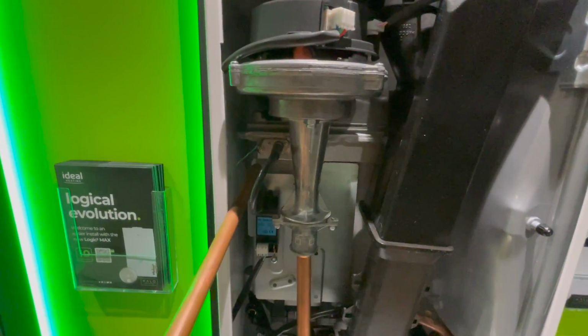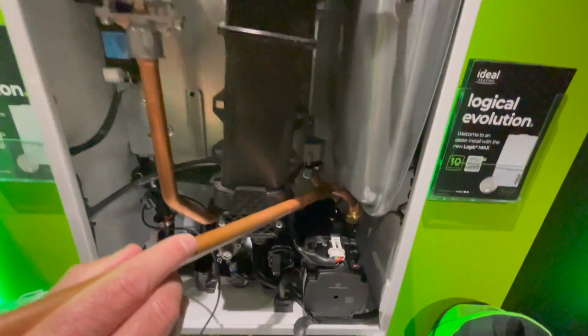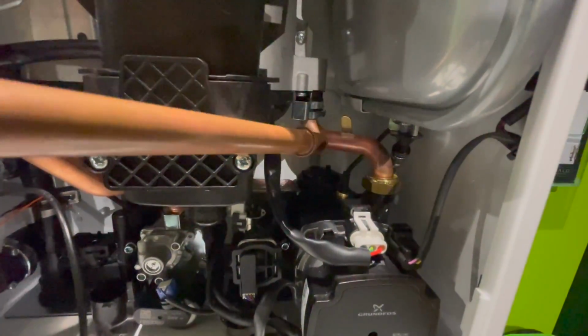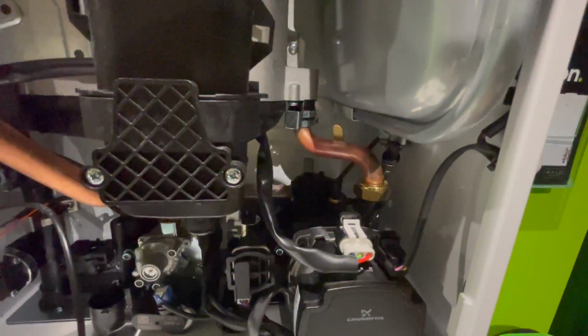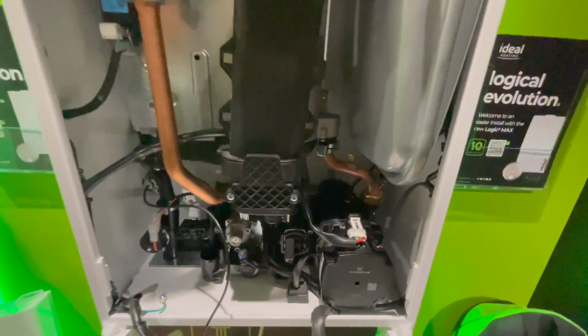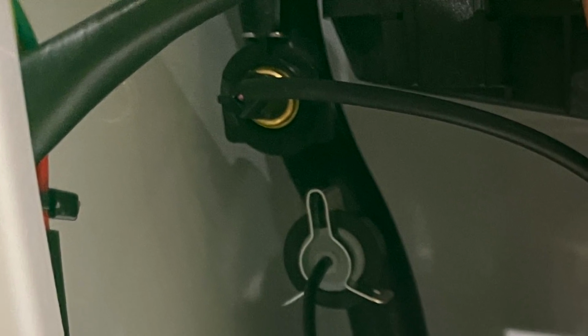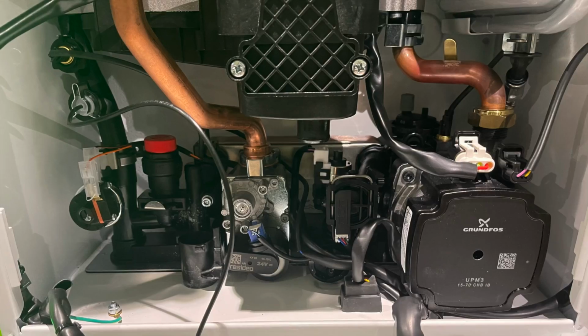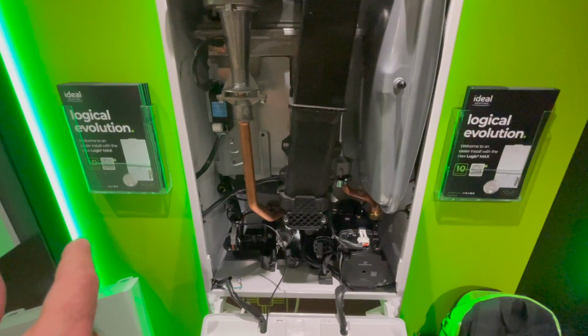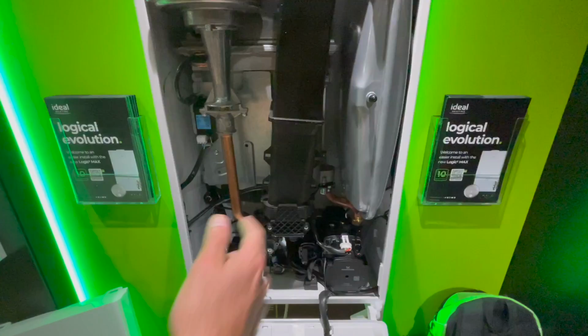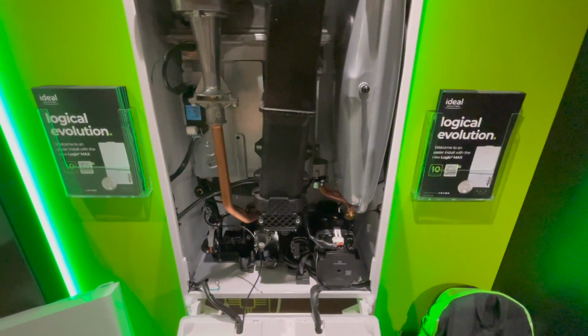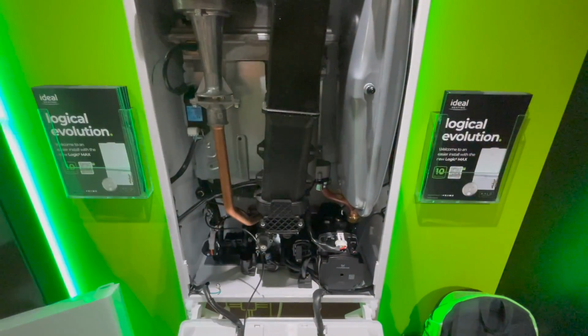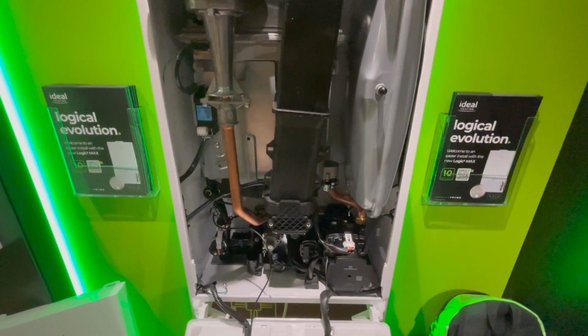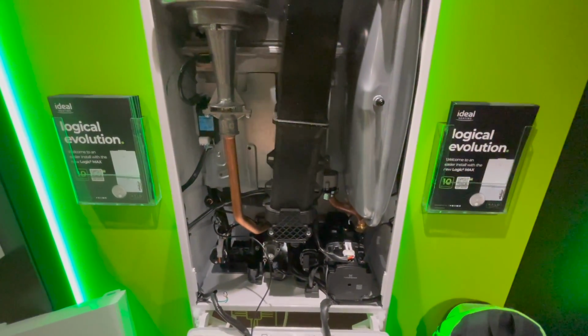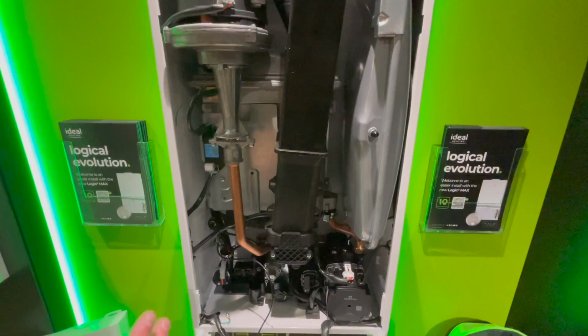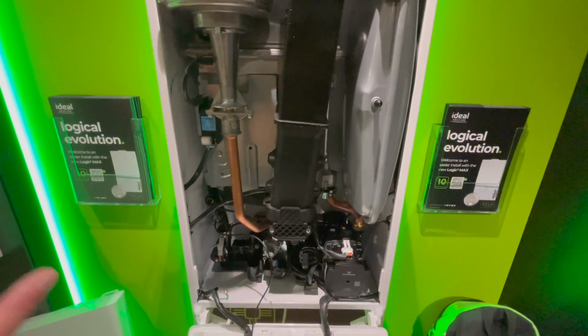So you can see the thermistor, what's normally here at the top, is missing, and the thermistor here, down here on the return, is missing. So they've now gone to 3 thermistors, one on the flow pipe, one on the hot water pipe, and one on the return pipe. Now the reason why they've done this is if you want to do preheated water on the old logic, you couldn't do it because the boiler wouldn't be able to sense the preheated water coming in, and it would spit out very, very hot water, so it would be dangerous.